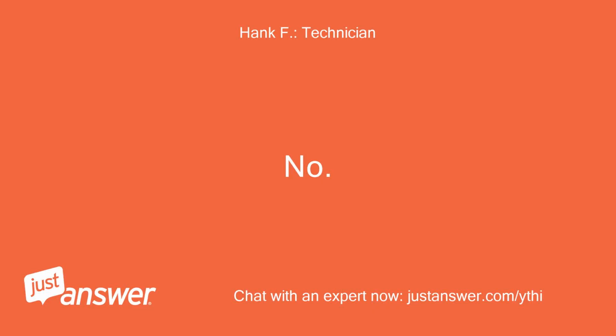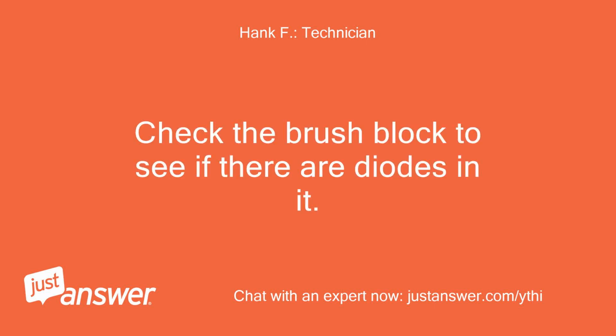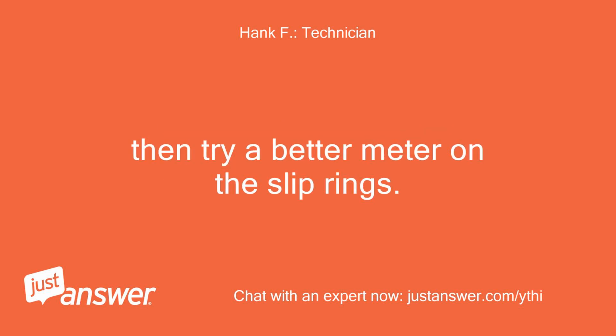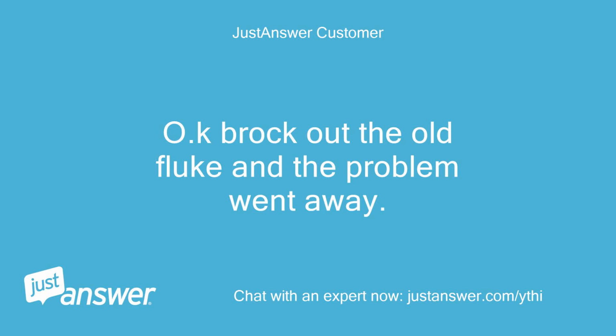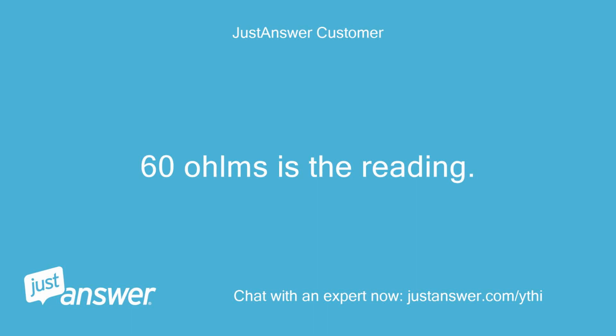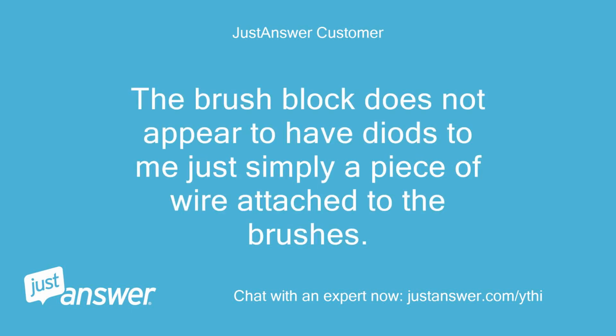No. Check the brush block to see if there are diodes in it. Then try a better meter on the slip rings. Okay, broke out the old Fluke and the problem went away. 60 ohms is the reading. The brush block does not appear to have diodes to me, just simply a piece of wire attached to the brushes.